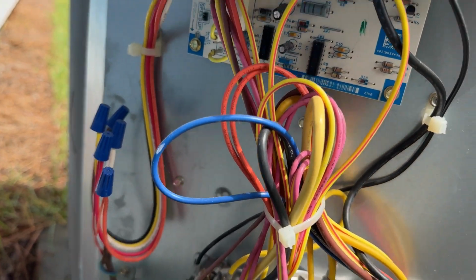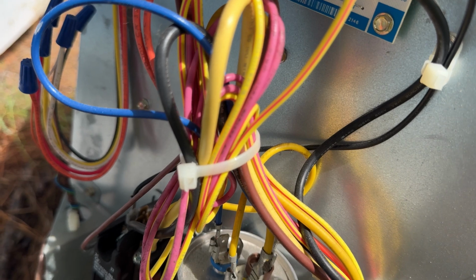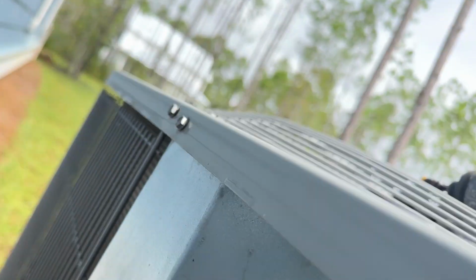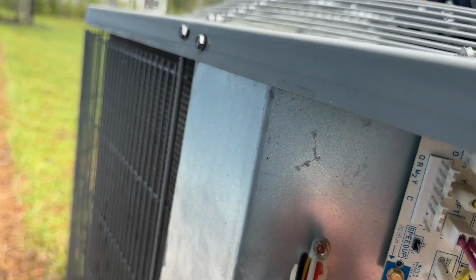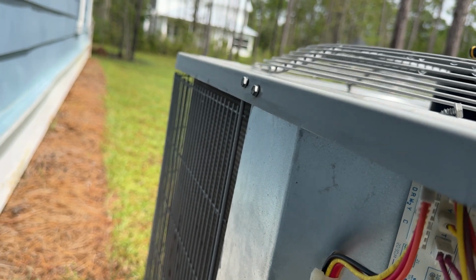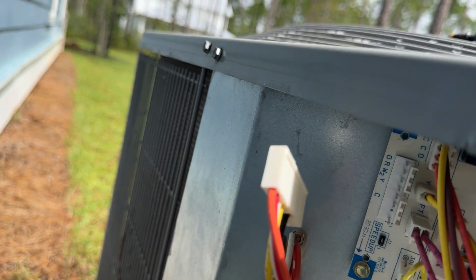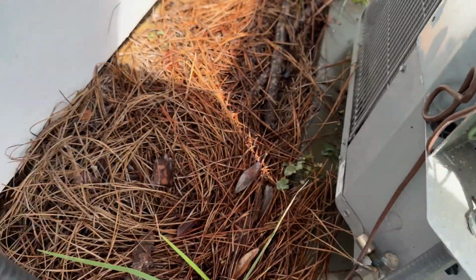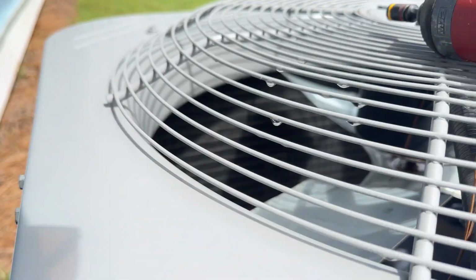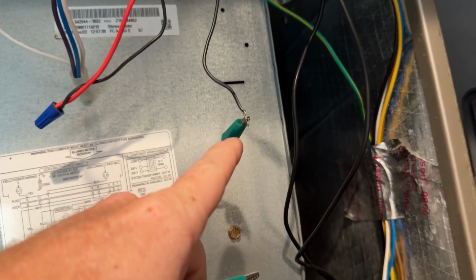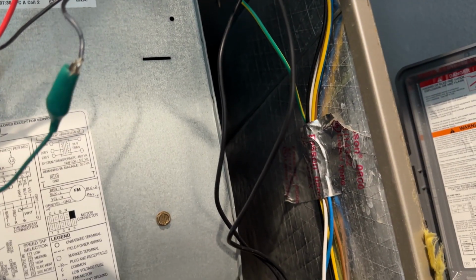So I'll do a visual inspection, check these wires. These orange wires here are usually reversing valve. I'm gonna say usually. Check your schematics and double check. They go up to here in the board, but if you really want to know if it's beyond the board, you can take that off and do your troubleshooting again on the inside, and then see if it's tripping. If it's not tripping, that means there's no short in your line coming out here, but it's in here somewhere. So after that, our next one's going to be this. We take this top off. Getting the power. Make sure you reset. And then you just touch them. Now.